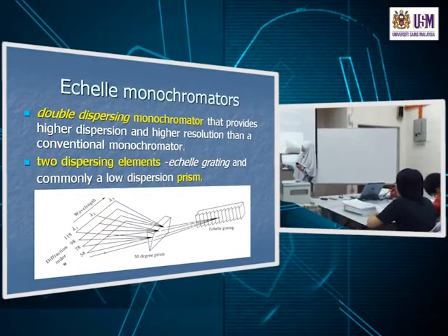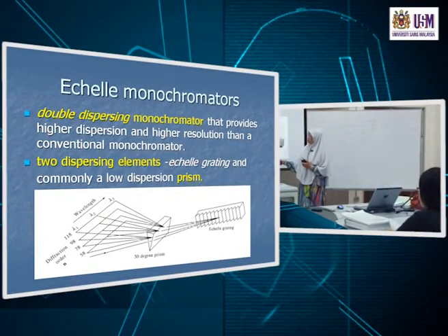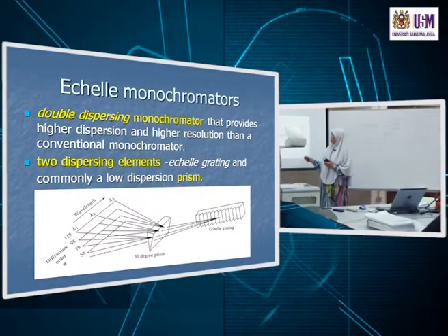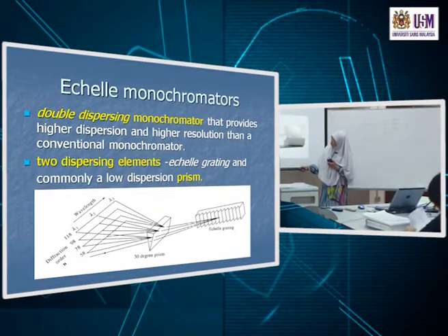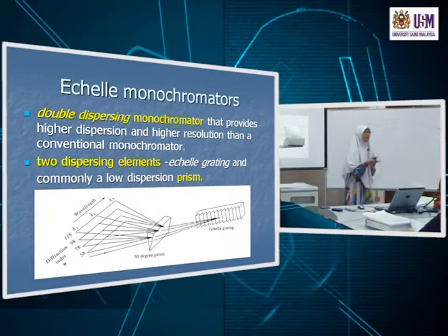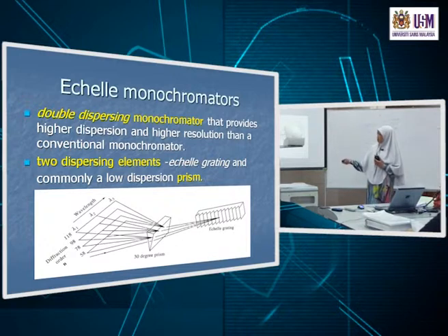So if you want to see that, this group of lines is at a particular order from the grating, similarly this one, so they are all different orders with different wavelengths. That's why the diffraction order is shown here: in fact, you don't work with n equals 1 and n equals 2. You are working with higher orders when you use the Echelle grating. If you see here, order 58, 78, 98, 118. So you use the higher order wavelengths.